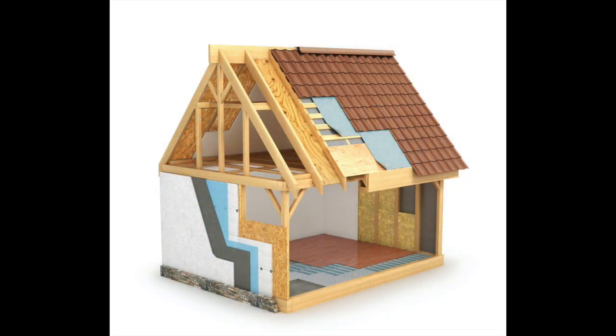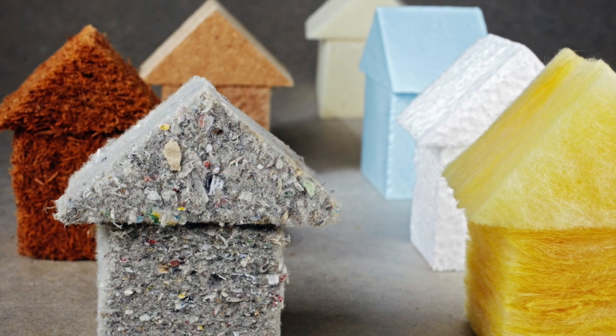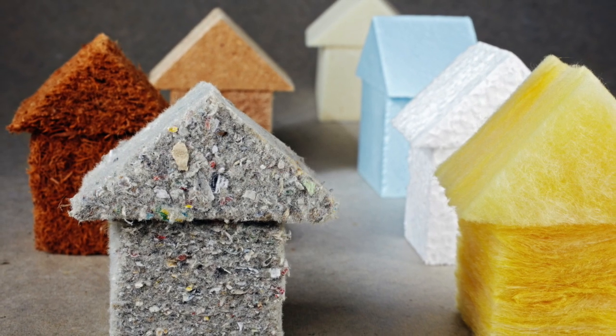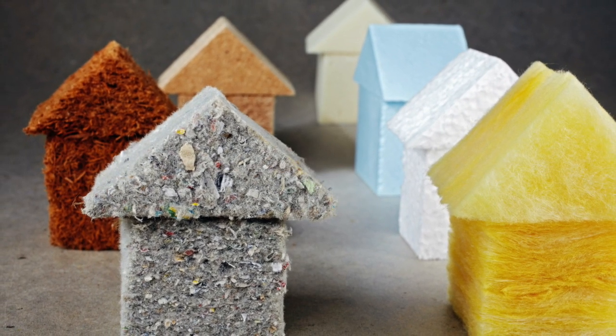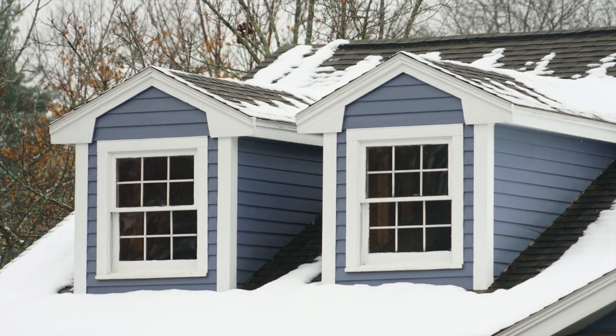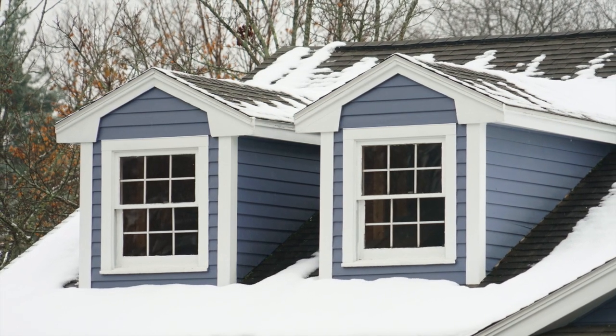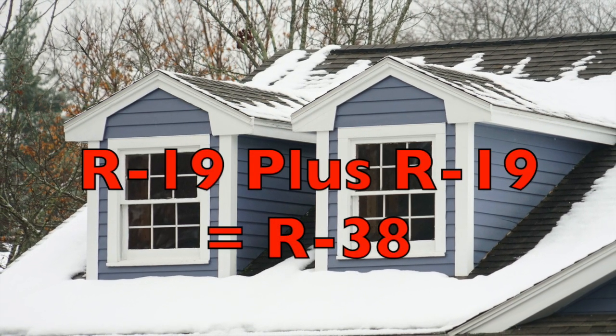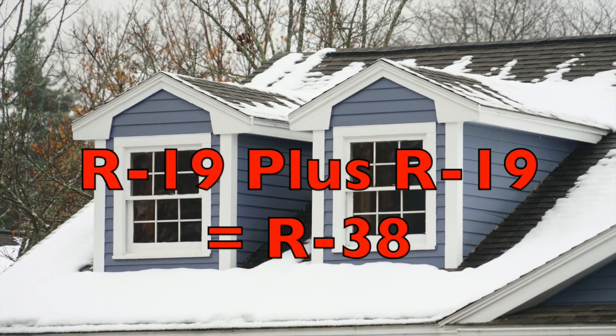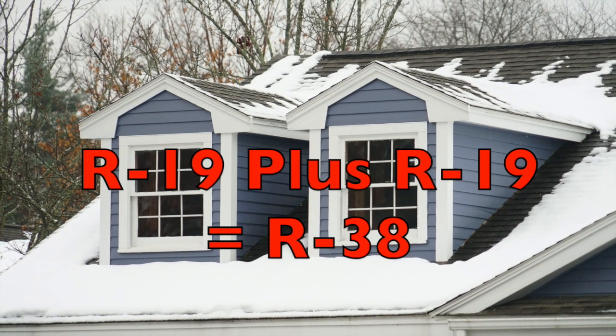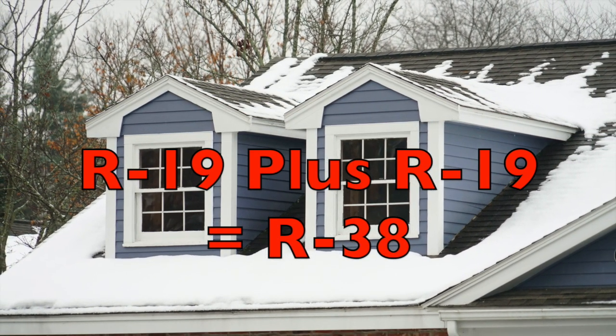Sometimes you need to add insulation to have the recommended R value. What you need to add will depend on the insulation type. To calculate R value, simply add together the R values of the layers of insulation. For example, if you have an attic with R19 fiberglass roll insulation between the joists, adding a second layer will give you an R value of 38.